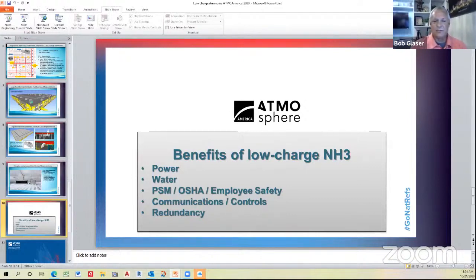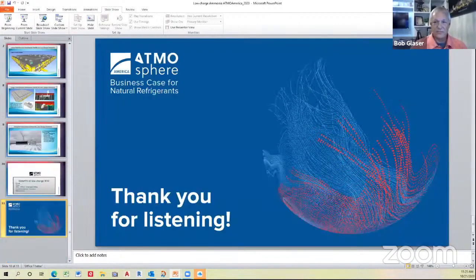Another big thing was a little bit of redundancy. Even where we have 20 below zero on an ice cream freezer, we run two compressors in that same penthouse so we can maintain one and keep temperatures, and we can also go through defrost and keep temperatures. The benefits of low charge ammonia really fit within all our parameters and help the company save money. Over the next two years, with the daily, monthly, and annual report cards, we'll see what that looks like, but I see great things as far as our power usage. That's pretty much it for that system and that building.